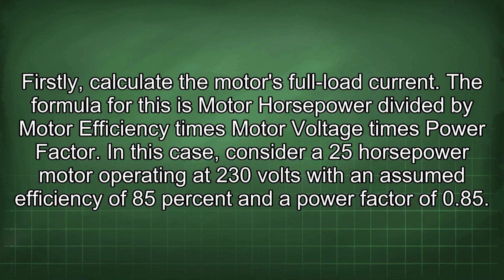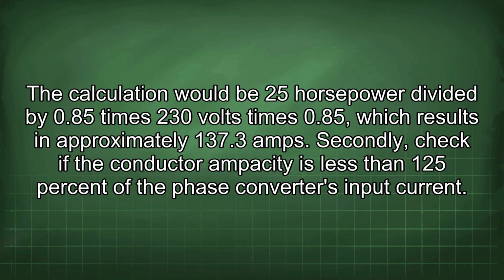Firstly, calculate the motor's full load current. The formula for this is motor horsepower divided by motor efficiency times motor voltage times power factor. In this case, consider a 25 horsepower motor operating at 230 volts with an assumed efficiency of 85% and a power factor of 0.85.